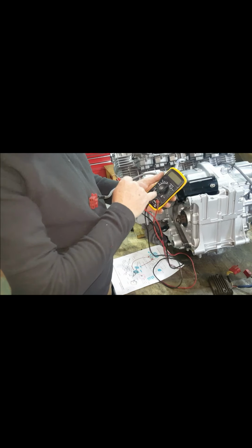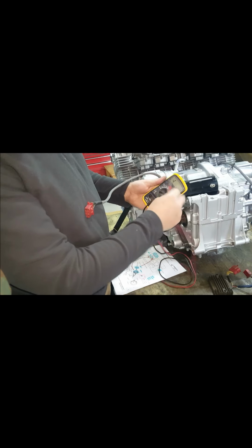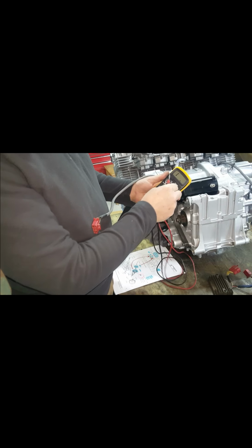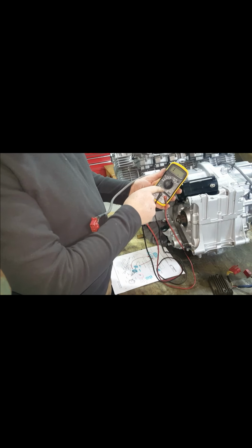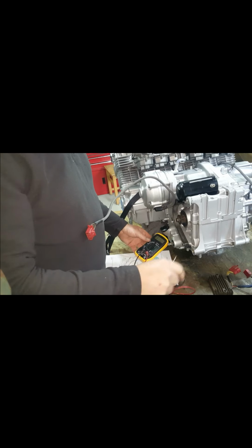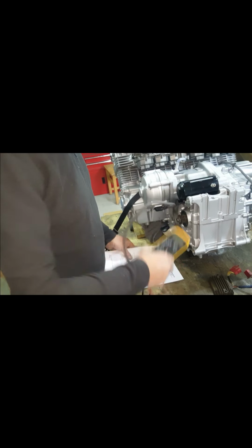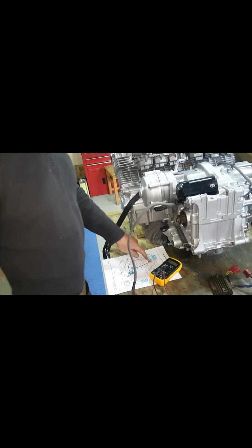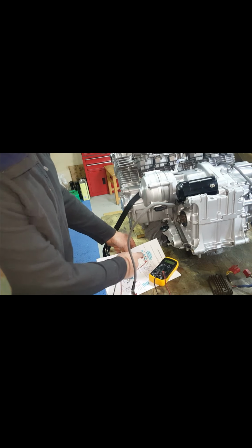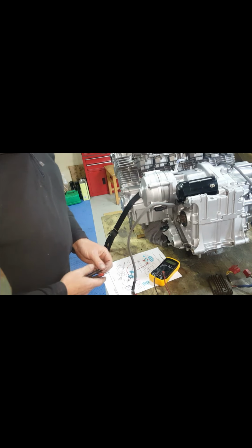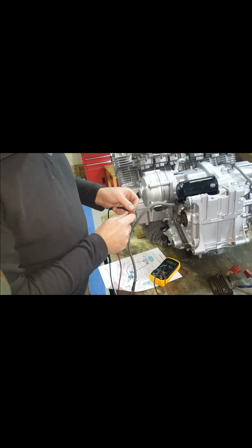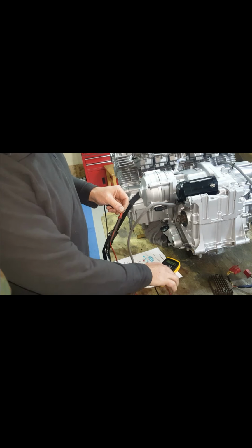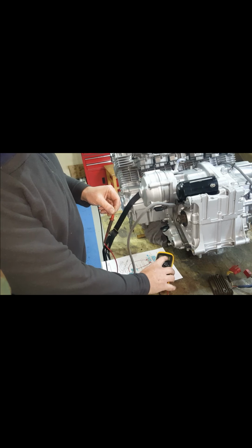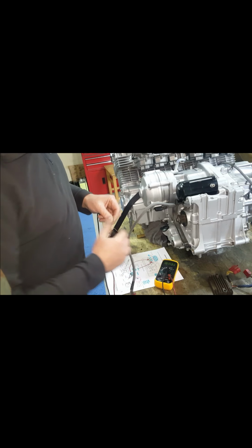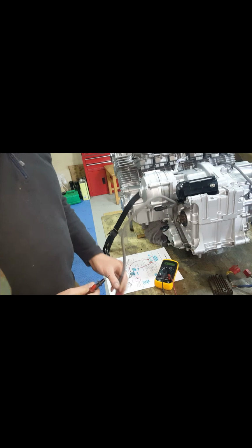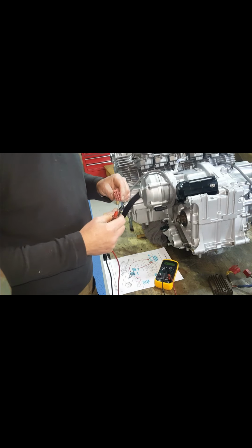Now what you need to do to test this is set it to 200 ohms, and then we're going to measure these windings on the diagram, which are under here. Before we start though, we've got to zero out our meter. You can see I'm getting 0.3 of an ohm, and that needs to be subtracted off the final reading to give us our readings.